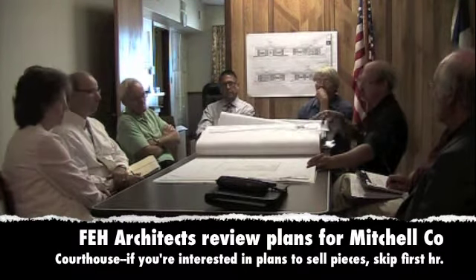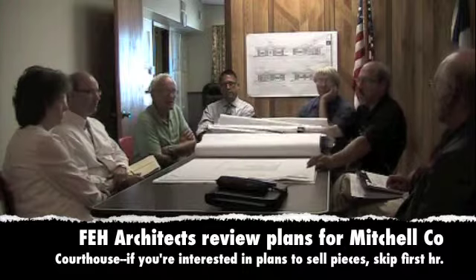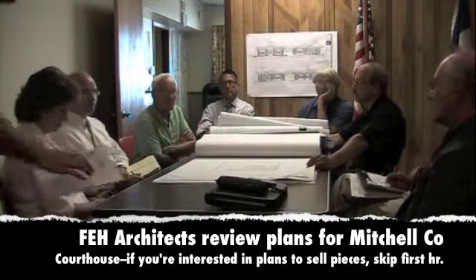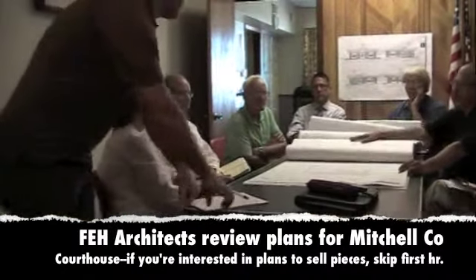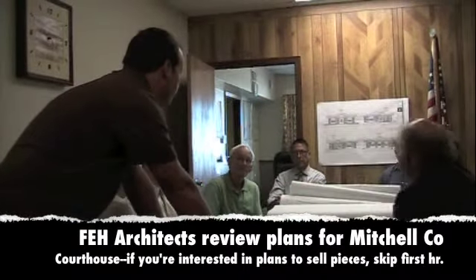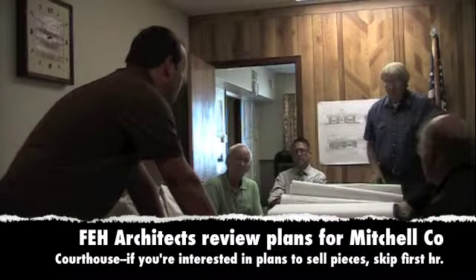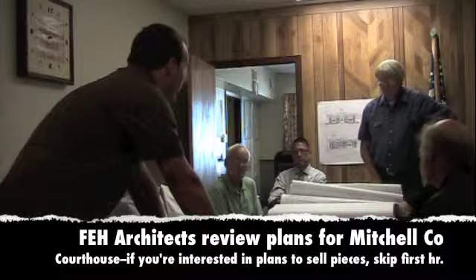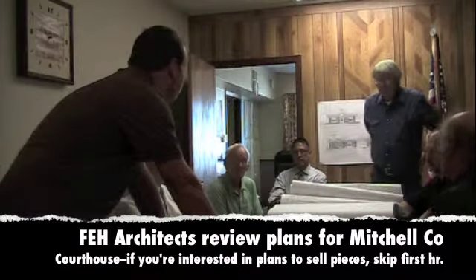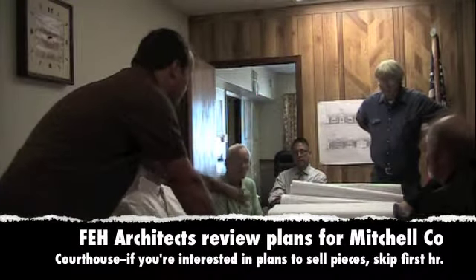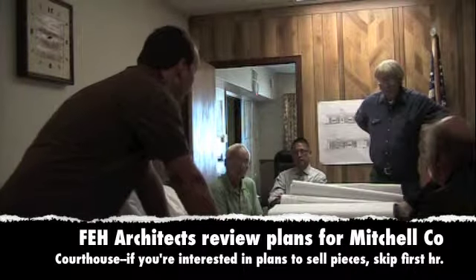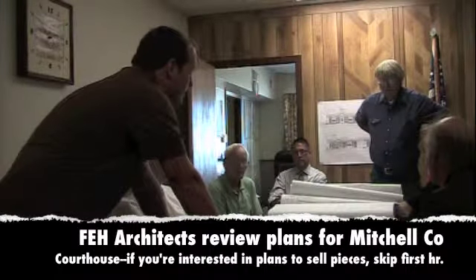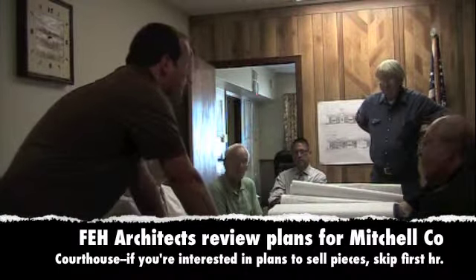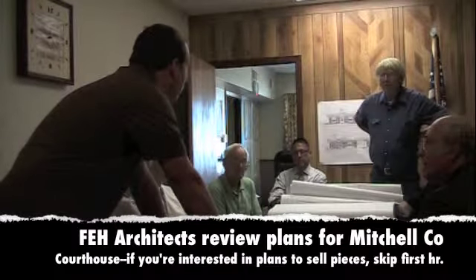Now, these are just the zones. Jake, you want to talk about these? Sure. Basically the hatching represents the hazard area, and it's based on the space classification. So if it's a storage room, it's going to have a higher density of sprinkler head coverage just due to what's being put in that space. And so that's what this really represents. We'll add some detail to this, and we'll detail certain areas where we're concerned about how sprinkler heads are going to look in certain spaces.